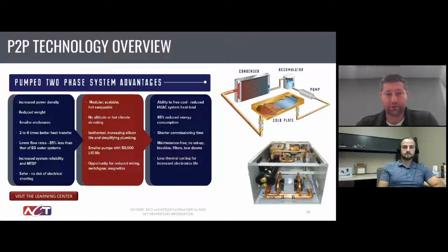Running through the loop: you have your cold plate or evaporator, where you're coupling to your power electronics and vaporizing the fluid. That fluid vapor is then pumped at some quality, a portion liquid and a portion vapor, throughout your system to the condenser, where it gives up its latent heat, condenses back, and enters an accumulator. The accumulator is sized such that you ensure complete liquid before entering the pump, and then you use the pump to create that pressure head. We'll talk about all the different components as we go through the system, but it's a fairly straightforward loop, and then we add complexity as we get into the design considerations.